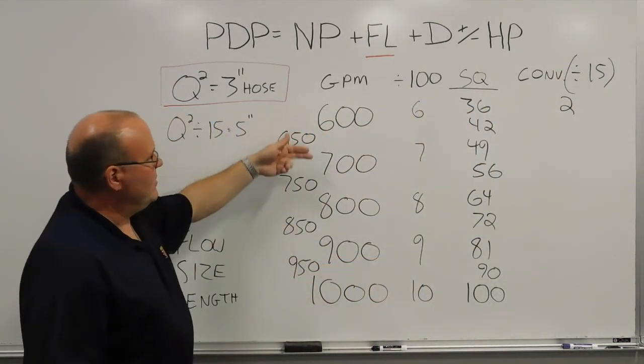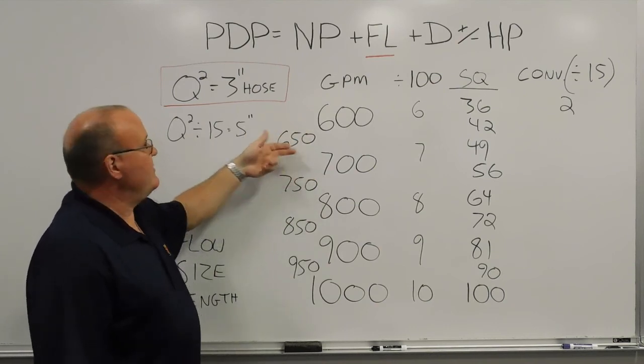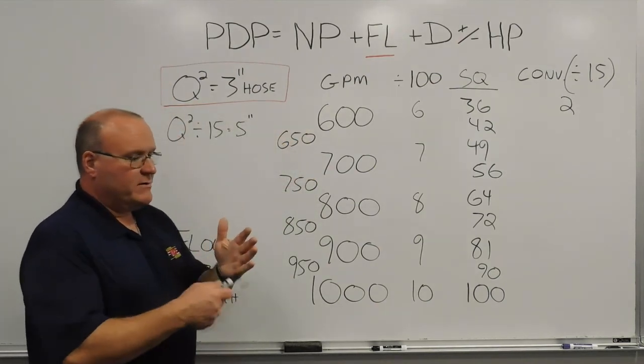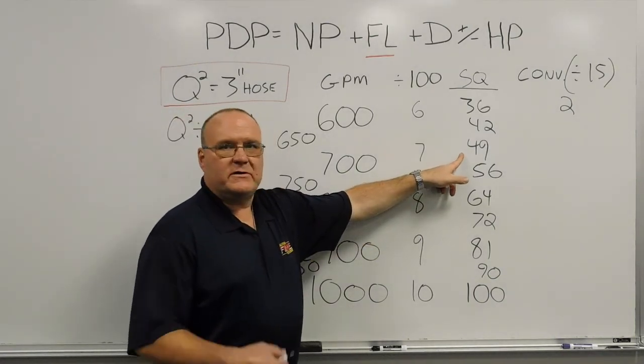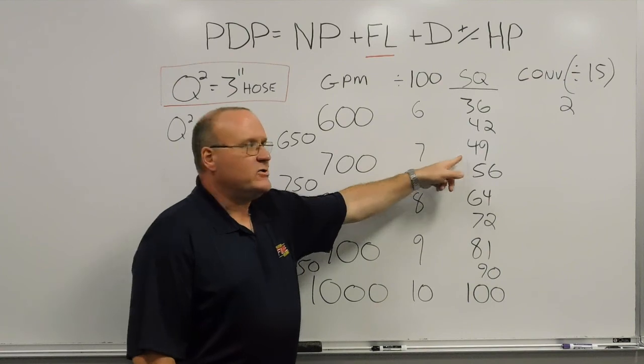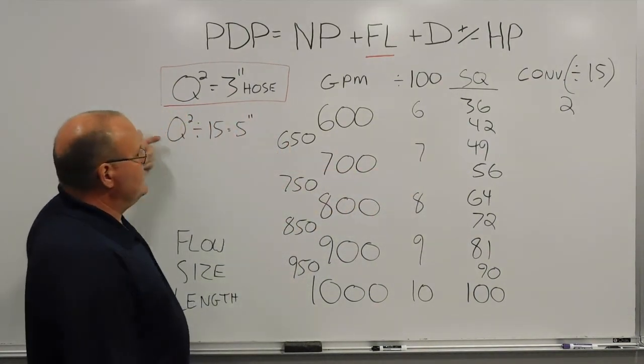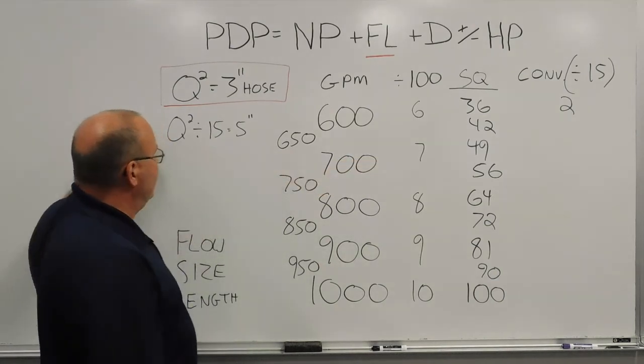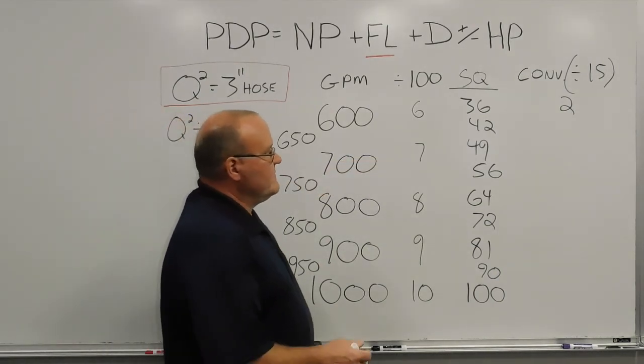When you come down here, and we'll stay with our whole numbers for now, 700 gallons a minute through 3 inch hose, Q squared, 7 times 7, there would be 49 pounds of friction loss for every 100 feet of 3 inch hose if we were trying to put 700 gallons a minute through it. For 5 inch hose, we divide 49 by 15, and you're going to end up with just over 3.